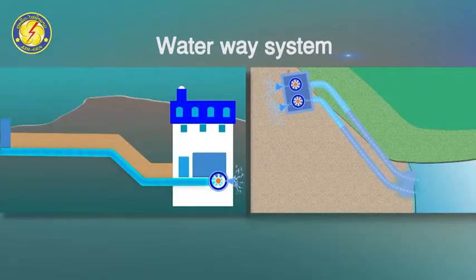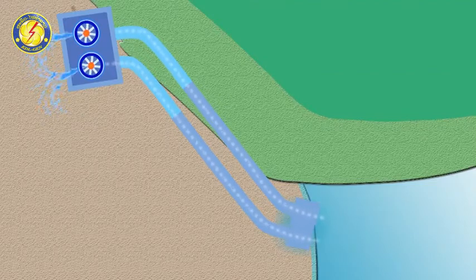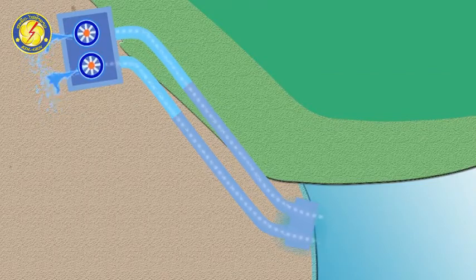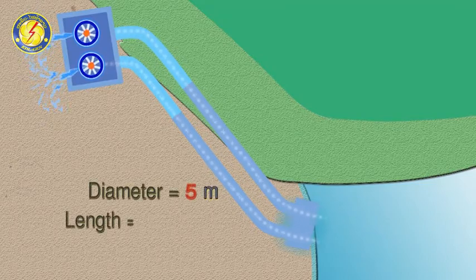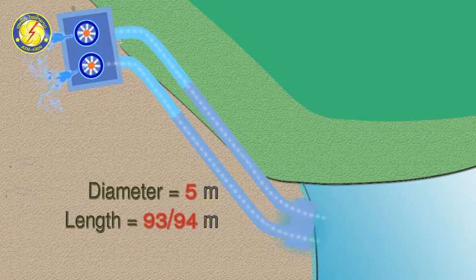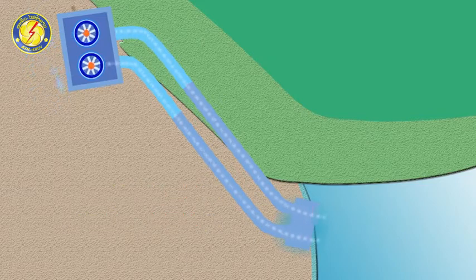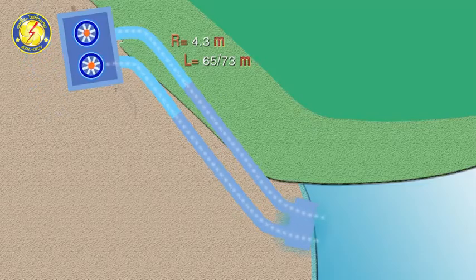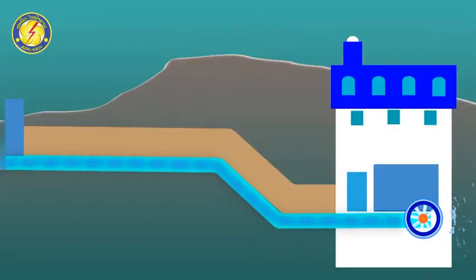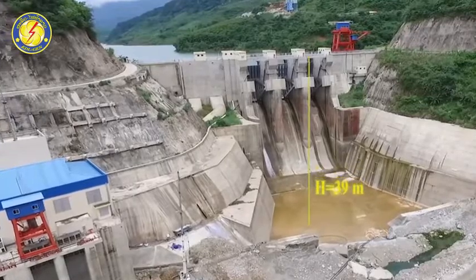Water intake and power tunnel: The power tunnel consists of a headrace, tunnel, and penstock. The tunnel is 5 m in diameter, and 93 to 94 m long. The penstock is 65 m and 73 m long, with a diameter of 4.3 m to connect with the water turbine. The design head is 39 m.